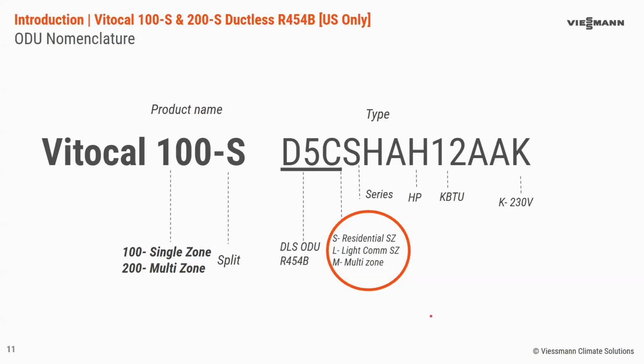Depending on the series will be the next two letters, but at this point, all of the series names are HA. H for heat pump. But the most important is really going to be the D5C, the letter after, and then your number here, which is your BTU. So with that information, you can say, all right, this is a 454B outdoor unit. S, it's residential, 12K. You know it's a 12,000 BTU single zone residential outdoor unit. Of course, you're not going to need to remember this. It's all in the documentation as well as the resources. But to have a better understanding of the model nomenclature, this is useful.